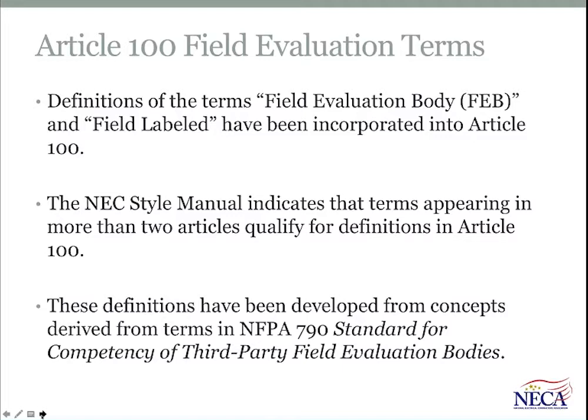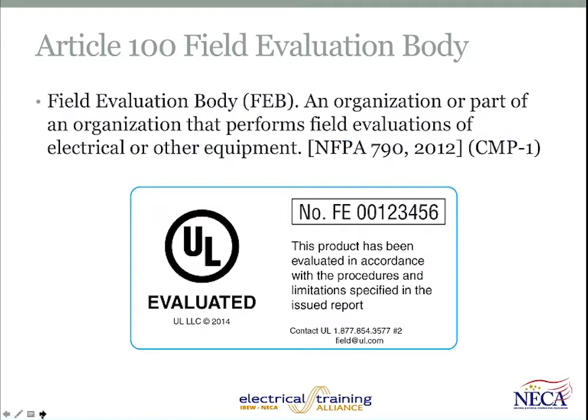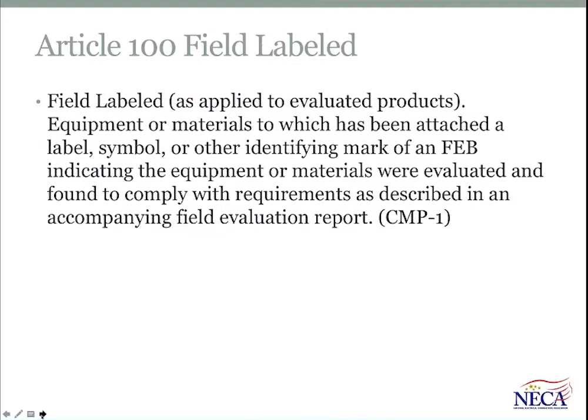So NFPA 790 has defined terms, field evaluation body and field labeled, that are now included in the NEC because they're used within rules that are governed by Code Panel 4, specifically in this case for large-scale photovoltaic systems. And one of the graphics that we have is a simple graphic that would represent an example of a field label that would be applied by the field evaluation body. And there you can see the actual definition. It talks about an organization that performs field evaluations of electrical or other equipment. Field labeled talks about equipment to which a label has been attached by the field evaluation body, and it indicates that the equipment and materials have been evaluated to appropriate product standards and are compatible with the NEC.